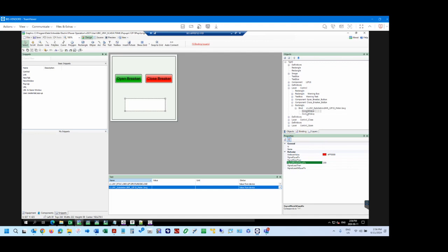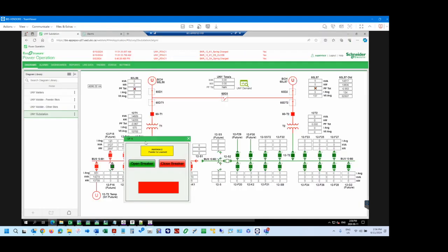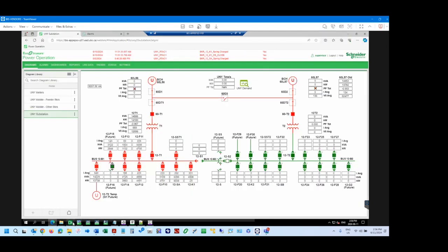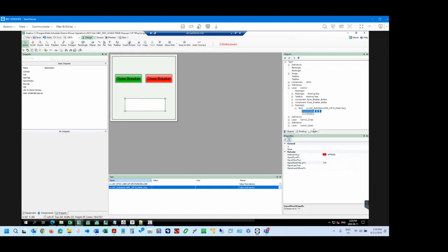Right now, I want it to go back to green because I'm basically saying, okay, it's not that loaded. I'm playing with the state right now. Basically, I just want to say if it meets the threshold of 200 amps, it's going to be red. I wanted to have a condition, right? And if it's not meeting that threshold, it's going to be green. Right now it doesn't meet that threshold, so I should get a green now. I convert values: 200 if it's more than, and less than 200, it'll be green.